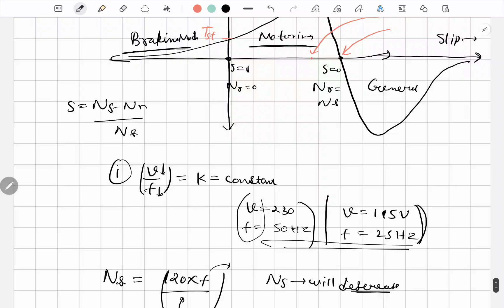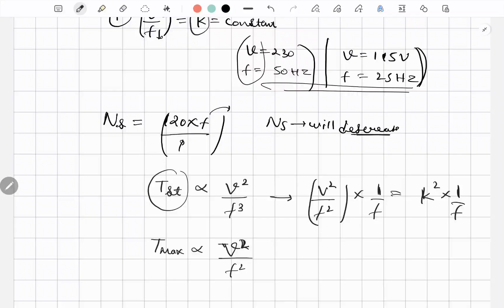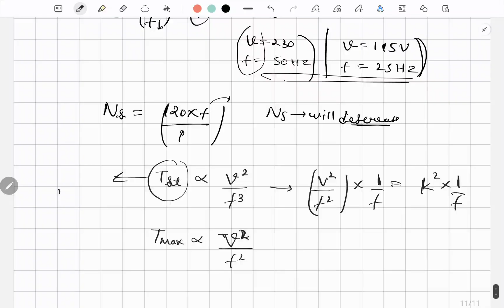Since the ratio of v by f we have seen is constant, we can write it as v square upon f square into 1 upon f. So this is k square into 1 by f. So we can see that the starting torque is equal to k square upon f, where k is a constant. Now we are decreasing the frequency, that means the starting torque increases. Also, the maximum torque is directly proportional to v square upon f square. So we can write it as k square, so it remains the same.